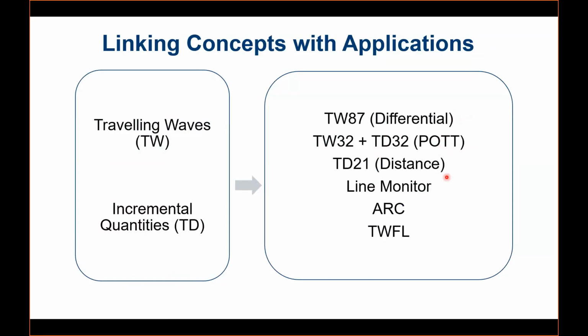Distance protection has been used to protect lines for a very long time. We have some innovative advancements in the distance elements that make them much faster compared to the conventional elements. Apart from protection, we have other features that are kind of the future of power system protection. We call them asset monitoring or line monitoring features. These are not currently available in the IEDs or protection relays we have for the line. So we either need to depend on dedicated devices, or on visual inspection or preventive maintenance, to detect incipient faults, the faults that haven't happened but are going to happen in the future. Line monitoring is very important, and it will tell you the weak points in overhead lines or cables that are susceptible to failing in the future. So it will help you in predictive maintenance as well.